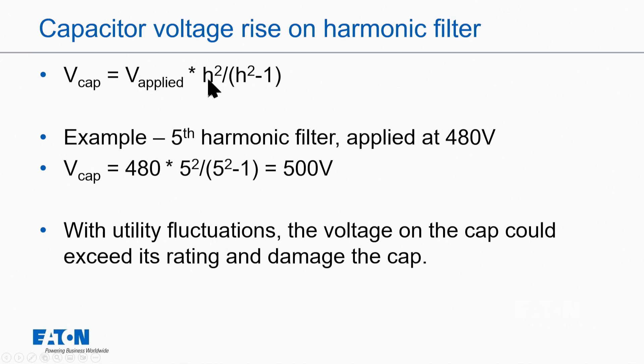In this example, if it's a fifth harmonic filter, it's just the voltage applied times the harmonic order you tune it to over the harmonic order squared minus one. So H squared over H squared minus one.